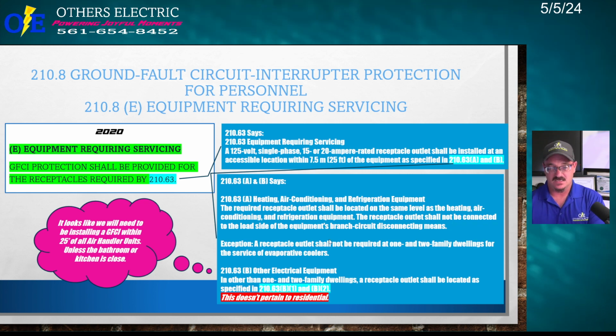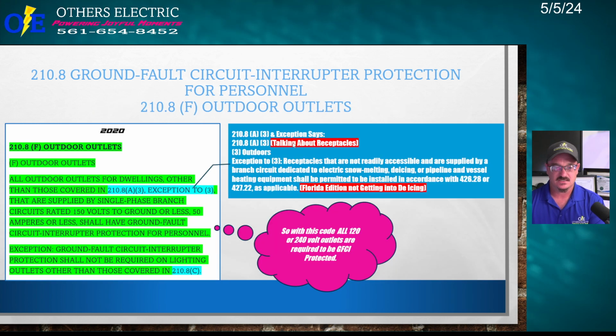Okay? And then B says other electrical equipment. In other than 1 and 2 family dwellings, a receptacle outlet shall be located as specified in 210.63B1 and B2. This doesn't pertain to residential, so we're not including it. Okay? So the major thing here is the equipment has to have a GFI for servicing. So air handlers and outdoor condensing units. Okay, let's see what the next slide says.